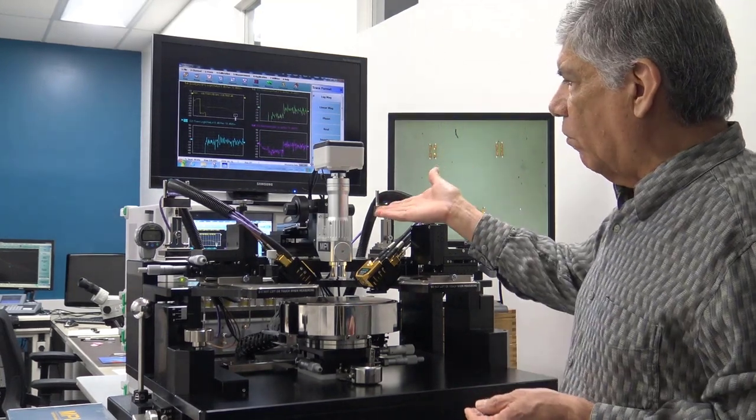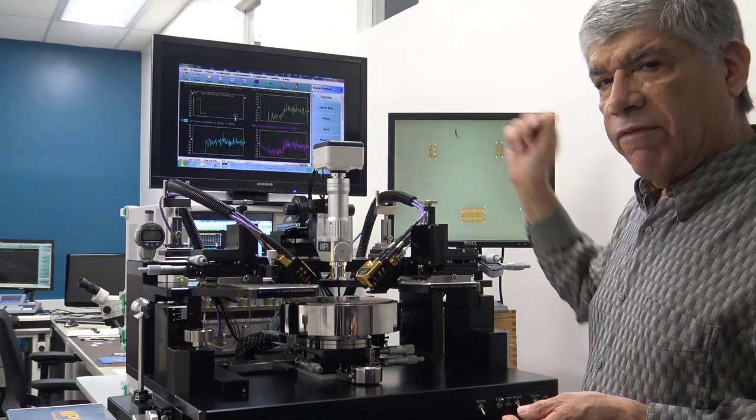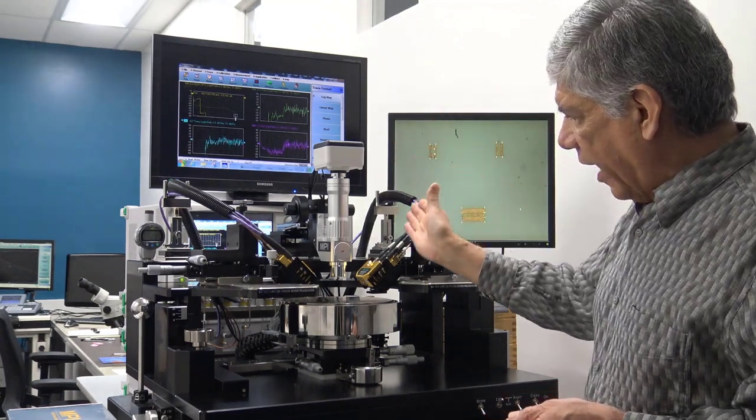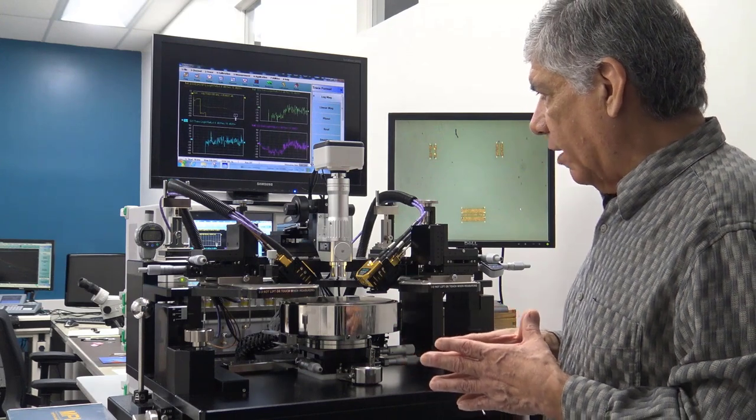The system is typically going to be set up behind the probe station. And normally you would want to elevate the test port of the VNA so that the cables have good access to where the modules are going to be mounted.